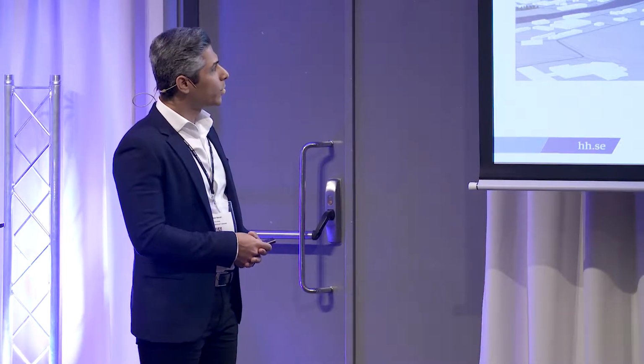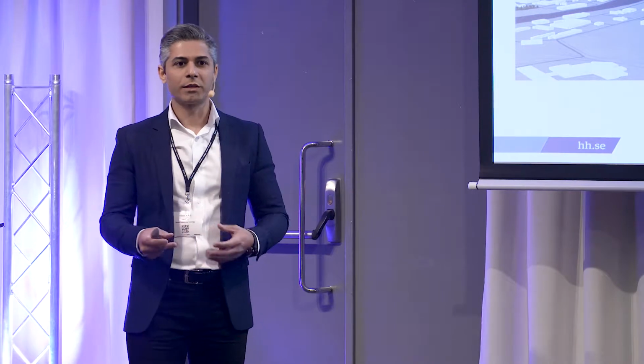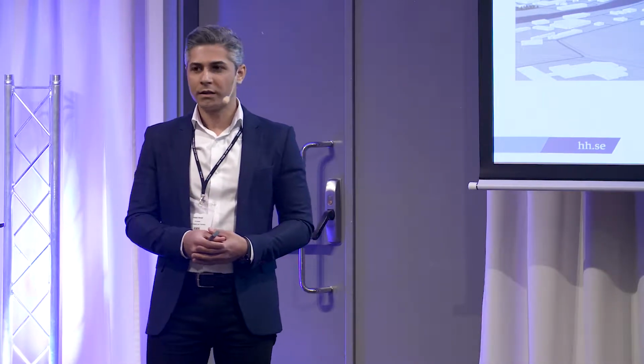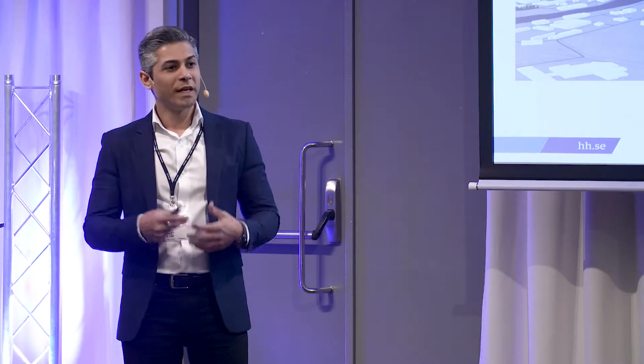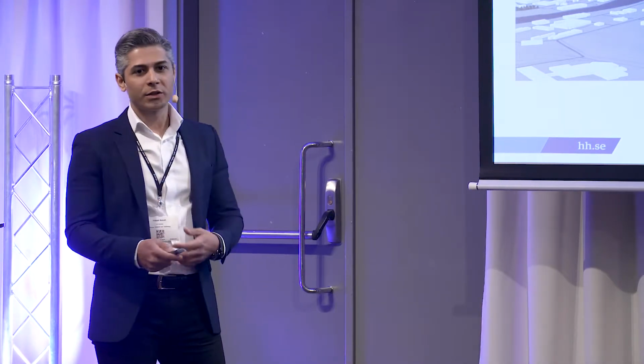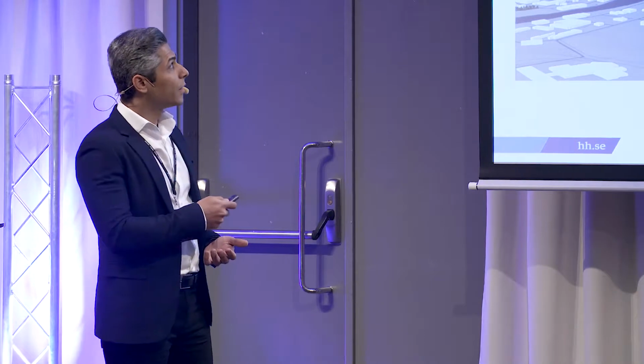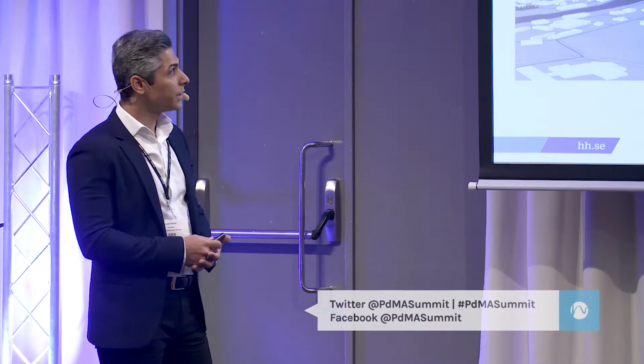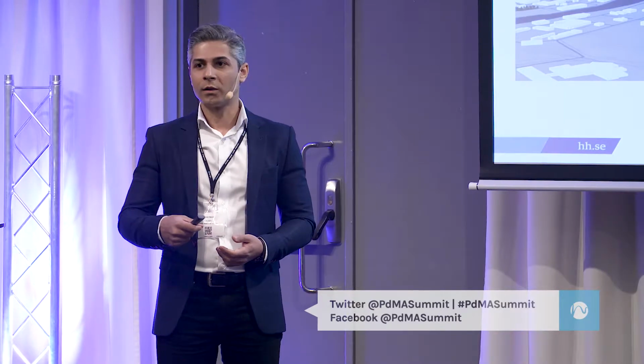In the next part of the project, we looked into the smart meters. Smart meters are electrical devices available at every household, used at the moment mainly for monitoring the electricity consumption. But actually, they can monitor other features such as power quality. So we modified more than 1,000 of these smart meters to be able to collect more data, especially related to power quality. And in case of power quality problems, usually these smart meters generate an alarm. So we use this information for detecting which areas in the grid would have more power quality problems.